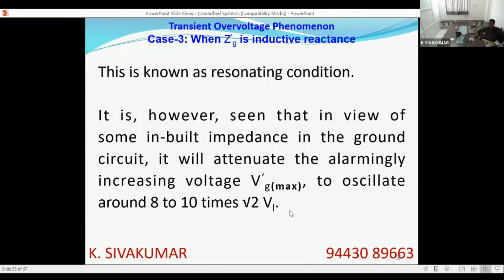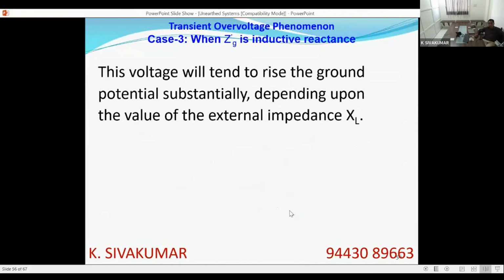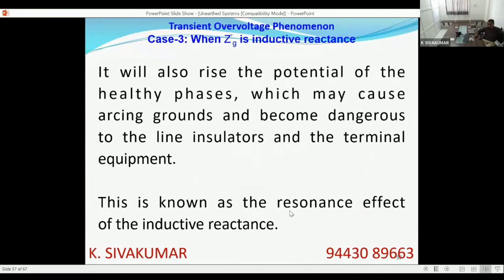It is seen that the voltage will float between 8 to 10 times root 2 Vl. This is a problem because our equipment is not designed for withstanding this voltage, so there is a chance of equipment damage and system damage. So this will raise the ground potential substantially depending upon the value of the external impedance. It will also raise the potential of the healthy phases, which may cause arcing grounds and become dangerous to the line insulators. This is called the resonance effect.